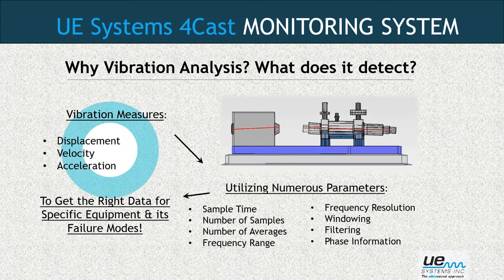Typically, the higher the speed, the higher the RPM of the equipment, the fewer samples and the fewer averages you need to get a good spectrum. The lower the RPM, so when you get into 300, 200, 100 RPM or below equipment, you need a lot more samples to build your spectrum, so that you've got enough to actually analyze it. So really, to get the right data for a certain type of equipment and its failure modes, you really need to be utilizing all these parameters and understand the actual function and operation of that piece of equipment.